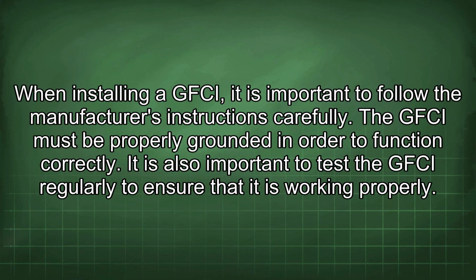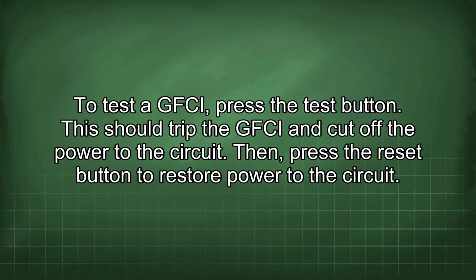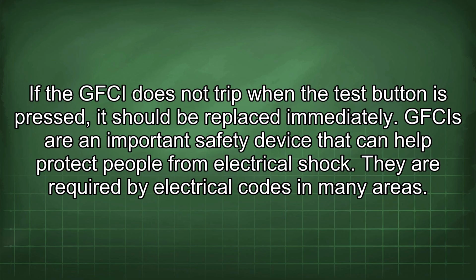When installing a GFCI, it is important to follow the manufacturer's instructions carefully. The GFCI must be properly grounded in order to function correctly. It is also important to test the GFCI regularly to ensure that it is working properly. To test a GFCI, press the test button. This should trip the GFCI and cut off the power to the circuit. Then press the reset button to restore power to the circuit. If the GFCI does not trip when the test button is pressed, it should be replaced immediately.